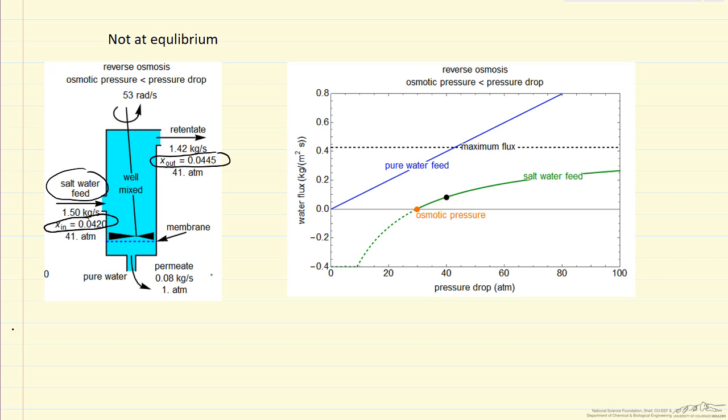Because we're getting pure water here in the outlet. And how much water we get out is a function of this pressure difference. The feed pressure, 41 atmospheres, and the outlet pressure, permeate pressure, is one atmosphere. So the figure on the right shows the water flux as a function of pressure drop across the membrane.